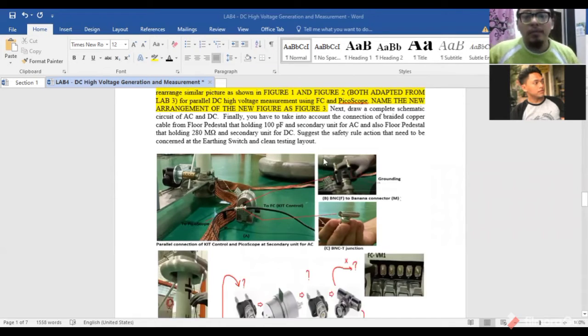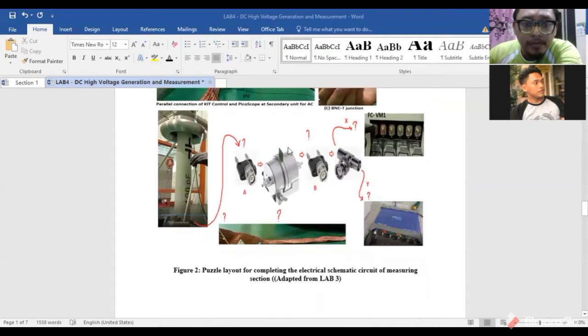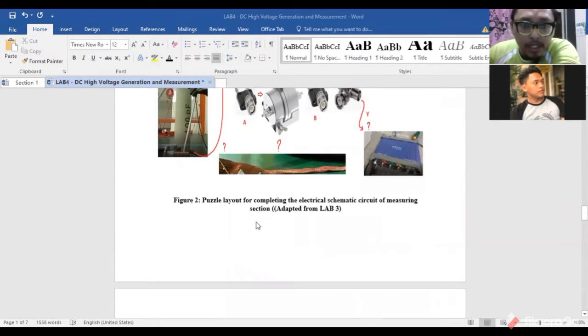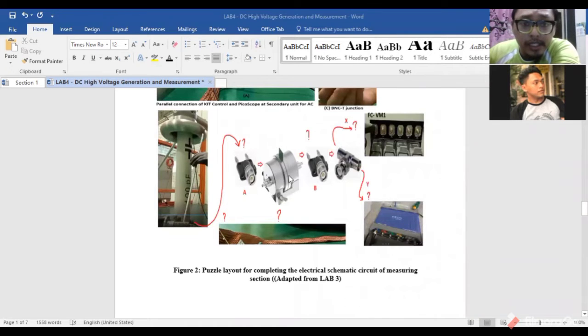Next, draw a complete schematic circuit of AC and DC. Finally, you have to take into account the connection of braided copper cable from floor pedestal that holding 100 picofarad and secondary unit for AC, and also floor pedestal that holding 280 mega ohm and secondary unit for DC. Suggest the safety rule action that need to be concerned at the earthing switch and clean testing layout. Now, this is figure 2. We can see that this is already done in lab 3.